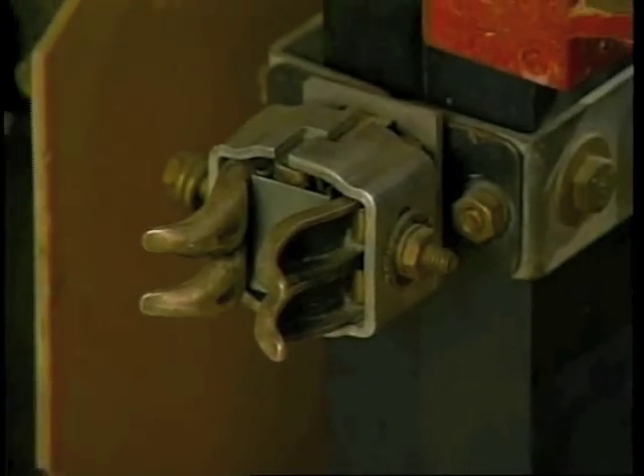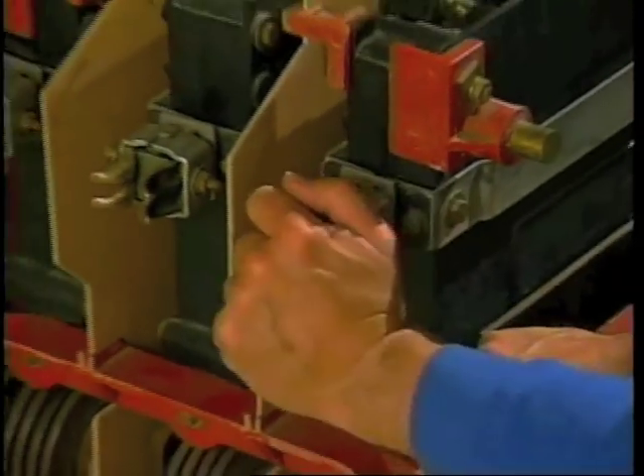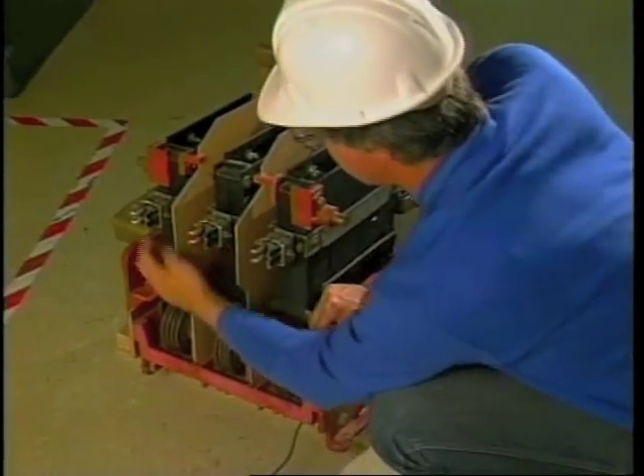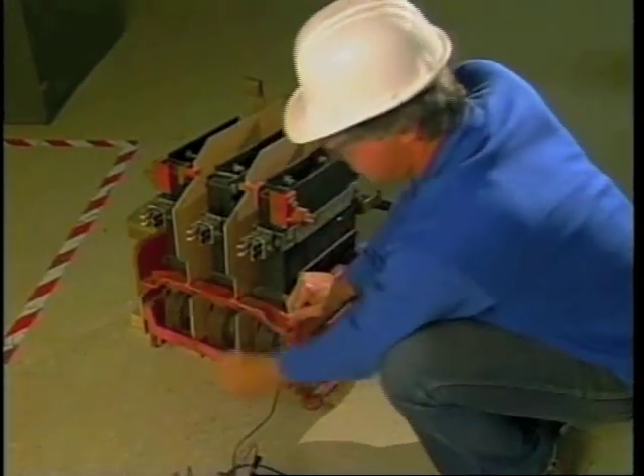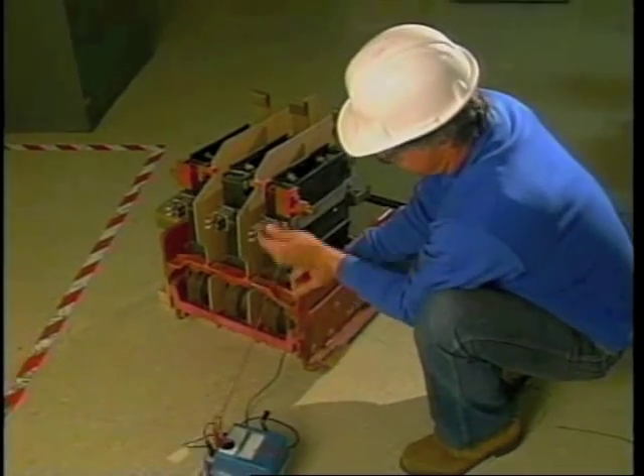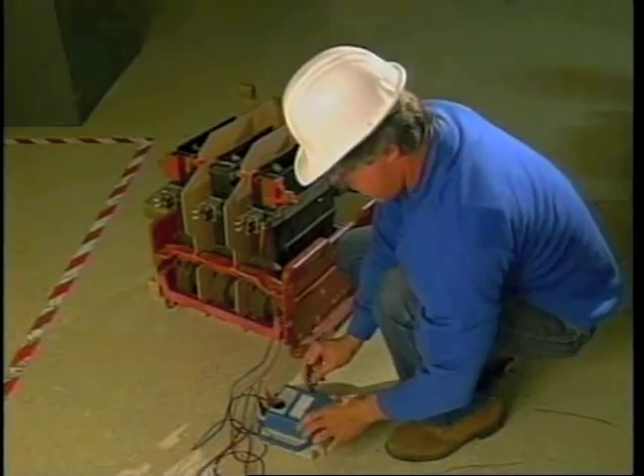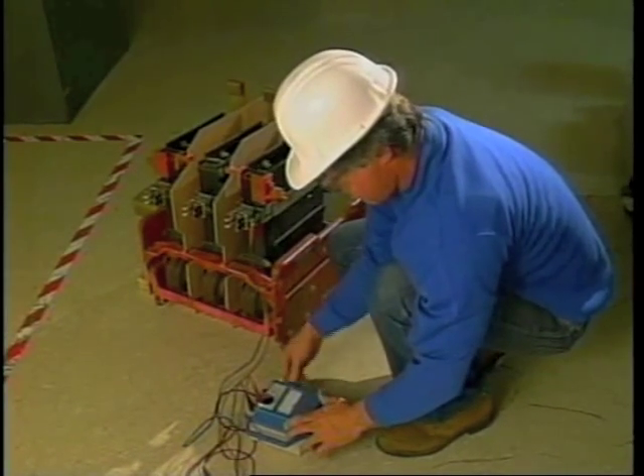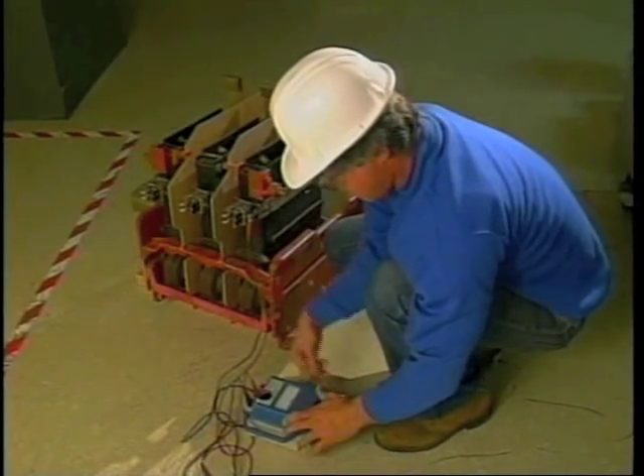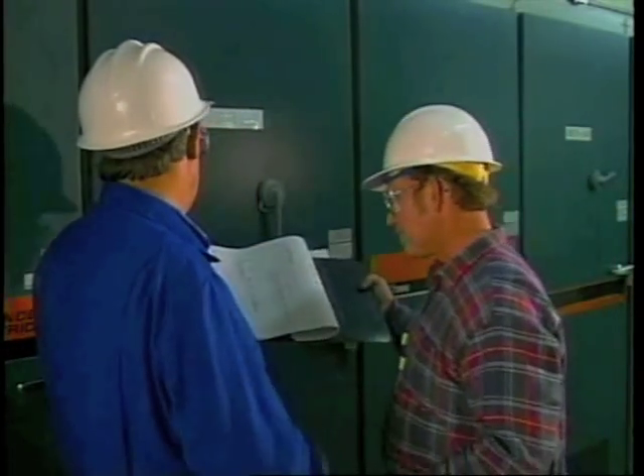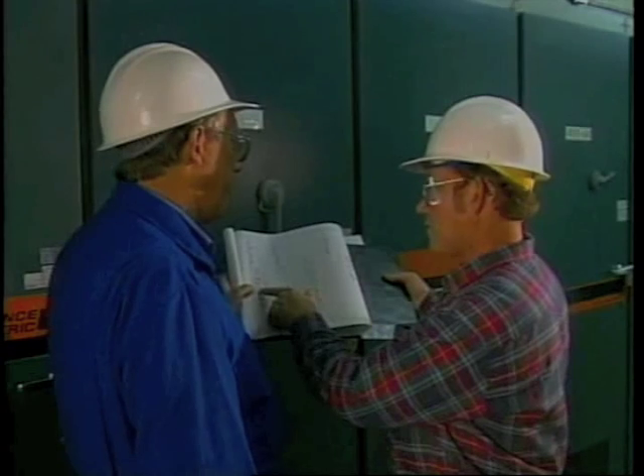A regular maintenance schedule must be established for contactors. The timing of maintenance depends on the frequency of operation rather than a fixed time schedule. Manufacturer specifications will indicate the need for maintenance on these devices. Let's review in detail the safe work practice for maintenance of contactors. Before removing or installing contactors, check that all possible sources of control power have been disconnected.